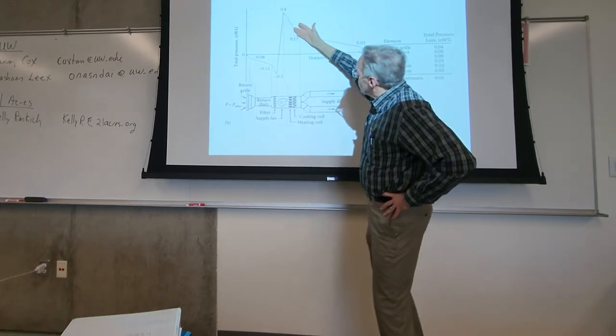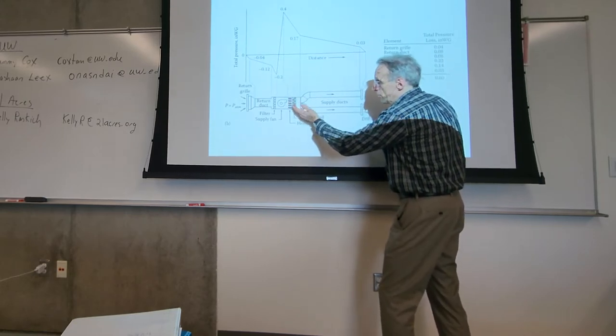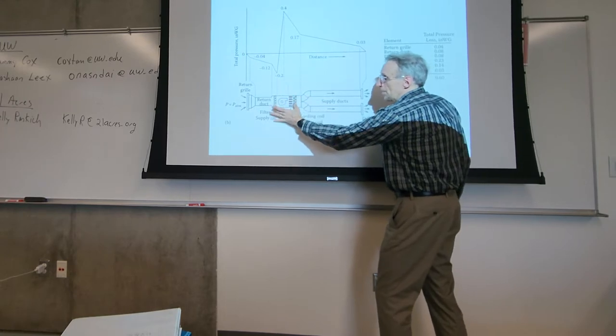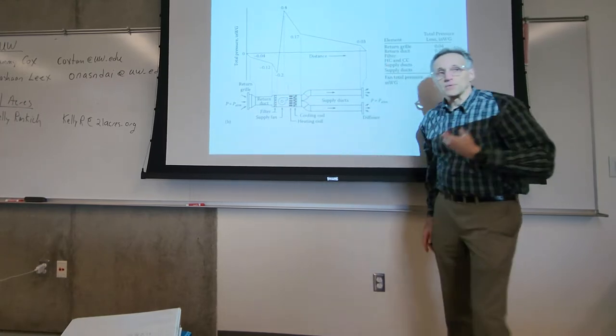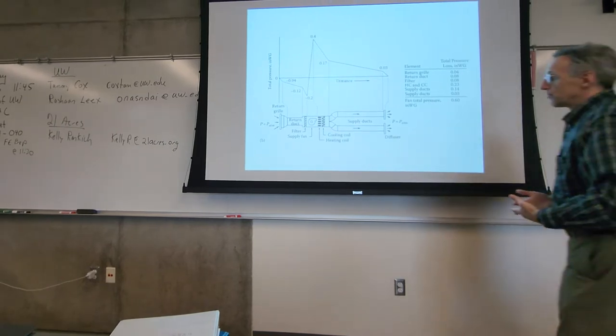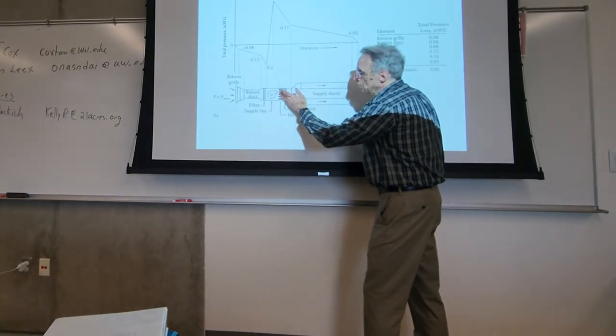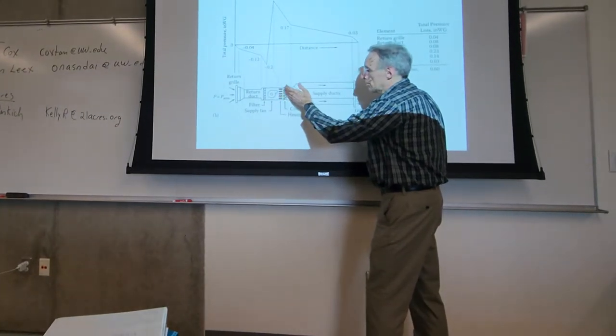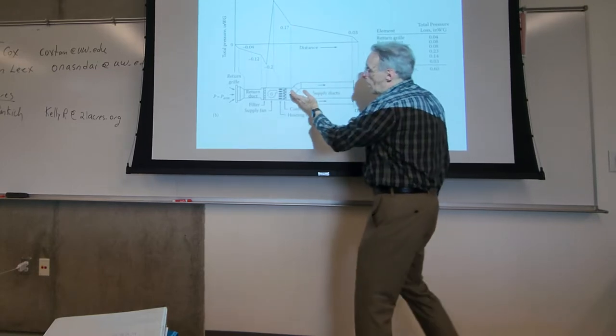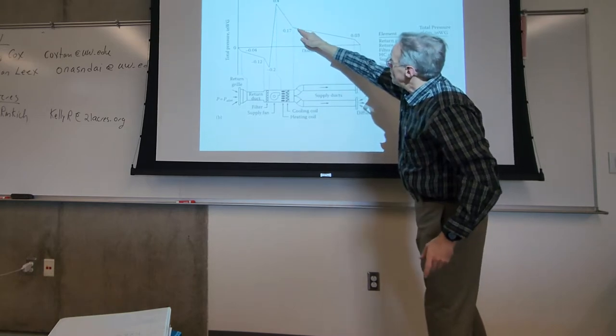And then you immediately start to drop as you move through, especially the coils here. Those are the filter and the heating and cooling coils. This is probably where you have the greatest pressure losses because you've got things that are just disrupting the flow. The air has to push around lots of little tubes here that have hot water or cold water or refrigerant. And then you come out with your nice conditioned air, and then you move through.